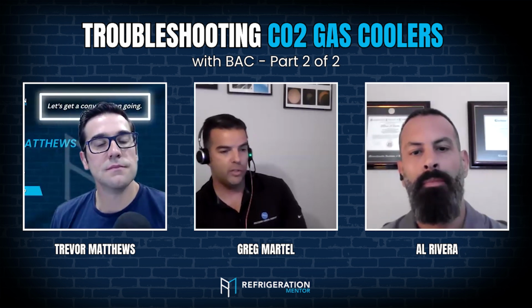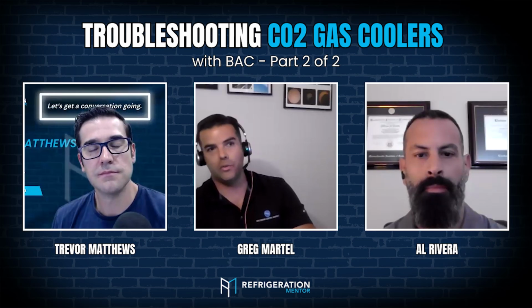So tuning the PID loop on a cold day, that's important. I know that startups are usually, or could be, during the summer, but it's important to go back in the winter time and make sure that things are stable. You don't want to see your fans cycling up and down. That's going to cause wear and tear on your fans, on your unit, on all your mechanical devices, that constant expansion and contraction. And we did a study about this a few years ago.